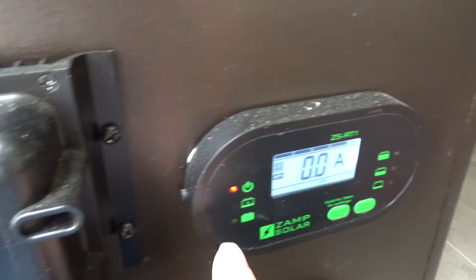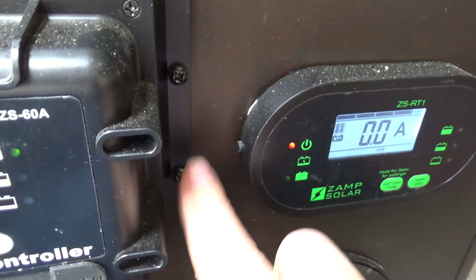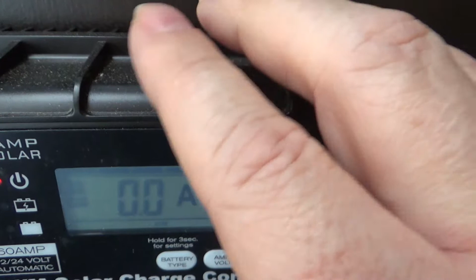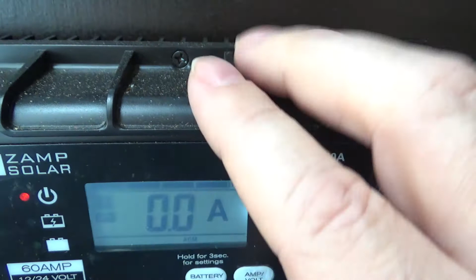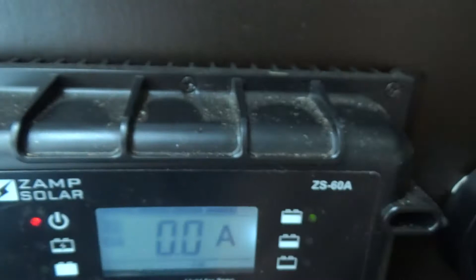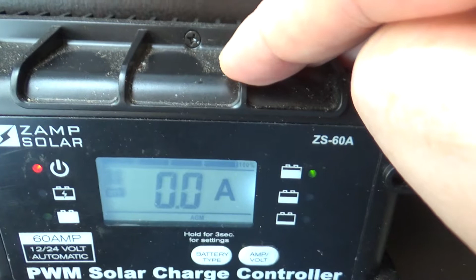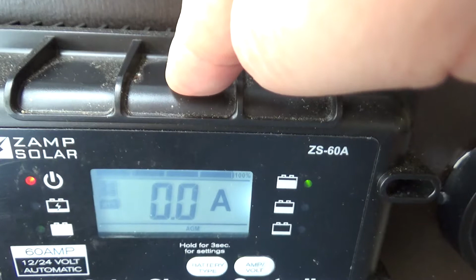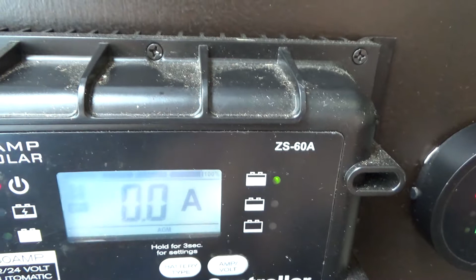Again, they put the remote system 3 inches - 1 inch - from the other one. So what happened here is this was going through one of those relays. ZAMP says connect directly to the batteries, do not pass go, do not collect $100, and Nexus did not install it based on the instructions of ZAMP. ZAMP says this has to go straight to the batteries. So if your solar charger is blinking - disconnect, connect, disconnect - that's because, one, the cables weren't thick enough, and two, the negative cable was hooked to the chassis.